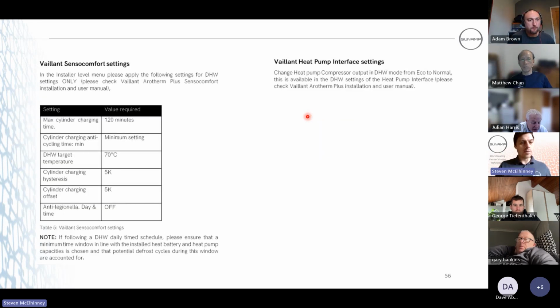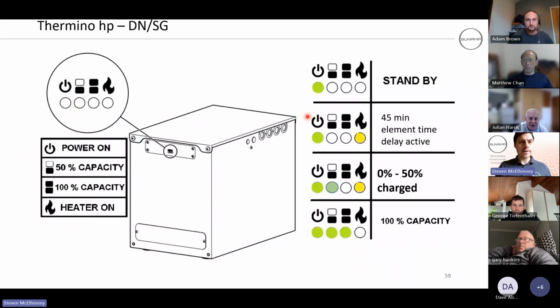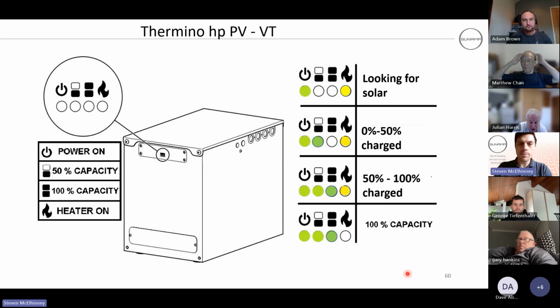Same with the Vaillant as well, from the Sensocomfort. Thermino-DN, after 45 minutes, the element LED will be illuminated, then it'll charge, get up to temperature. You might be lucky, it just depends on the conditions outside, what the heat pump can actually achieve. Oh, yeah. Your PV version of the Vaillant, again, it's going to be looking for solar. So that element LED will be illuminated more often than not. Same rules apply though. The heat pump will charge it up to 85% and it'll allow the last 15% to be charged from the element, whether it's PV or from grid.